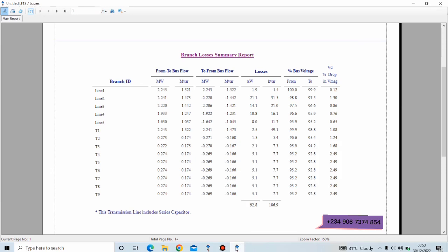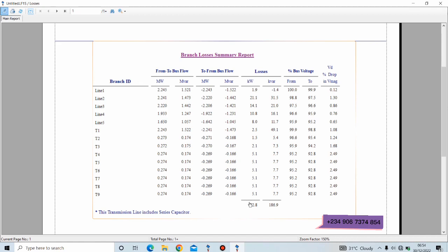The third aim of performing a load flow analysis is to determine the active power losses—the active power losses, which is this. This is the active power losses—the total power loss, active power loss, we're having 92.8 kilowatts. And the total reactive power loss we're having is 186.9. So we have achieved the primary aim of load flow analysis. We know the active and reactive power flow through various branches and loads, we know the active and reactive power losses, we know the bus operating voltages, and we also know the bus phase angles.